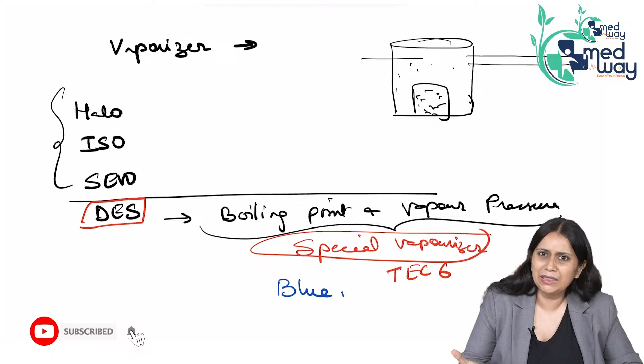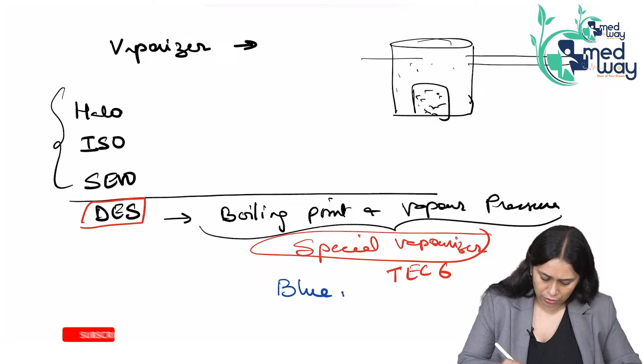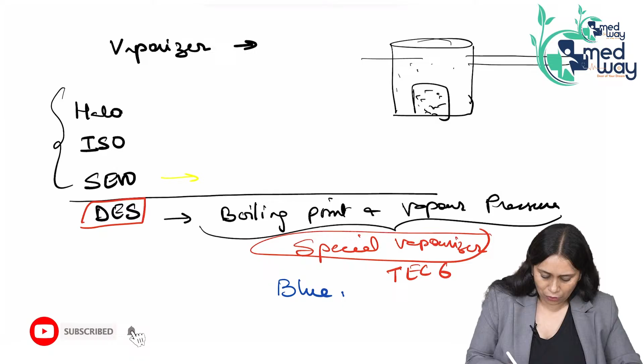The other three have similar vapor pressure and boiling point, but potency is different, and chemically they are different. So, we should not mix one agent with another, and they should also have specific vaporizers. Though the vaporizing technique is similar, the vaporizer is agent specific. So, again we need color coding to identify which agent's vaporizer it is. Sevoflurane, what color? You all remember sevoflurane is the best inhalational agent for children, and children like bright colors like sunshine yellow. So, sevo has a yellow color code.